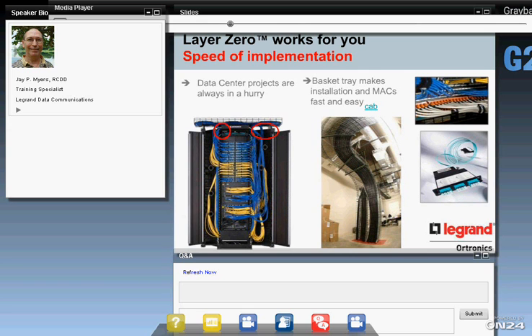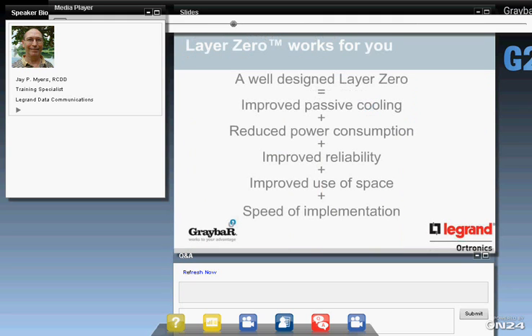Cablofil, and that's in the center there, is at least 30% faster to install than the traditional ladder rack. It also is open, so it allows better cooling of the cables, which is important as we go to more power over Ethernet as well. Okay, so even though this is just simple stuff, just bent metal, a well-designed layer 0 can dramatically improve passive cooling. It can reduce power consumption, improve the reliability of your network, improve use of space, and also speed up the implementation.